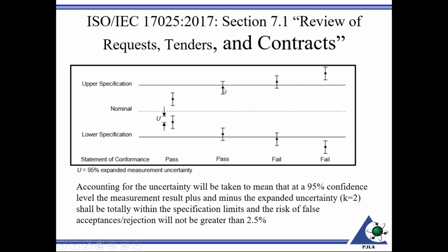Okay, this value here, you see where I'm pointing? That is the recorded value. So you're stating in calibration, if say it's a test weight, this test weight is 5.00031 grams, as an example. That's the value. This gray area is the uncertainty. So you always have an uncertainty. By definition, measurements are not traceable without an associated uncertainty. And you can see you have a value with that crossing over the spec limit there. So that's what we're talking about.